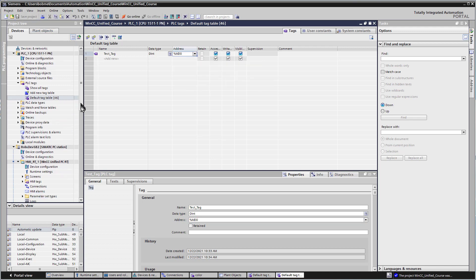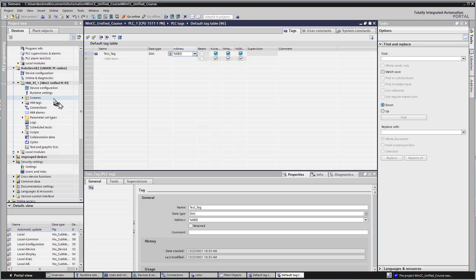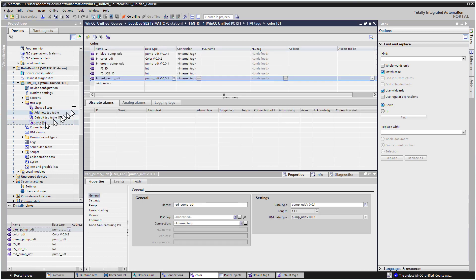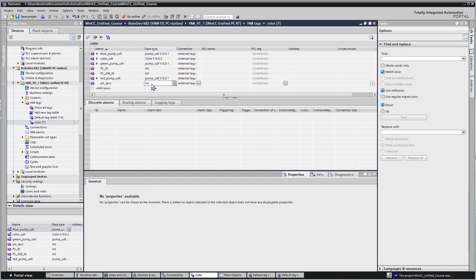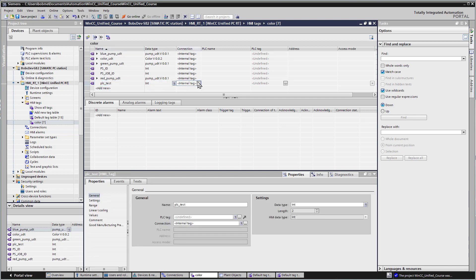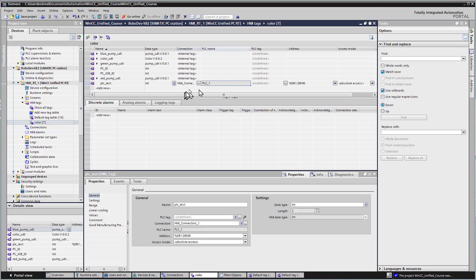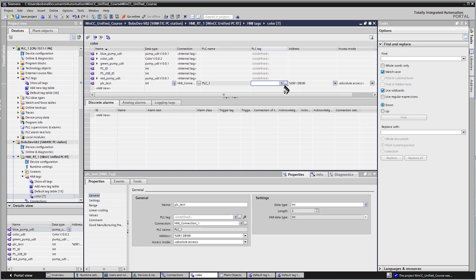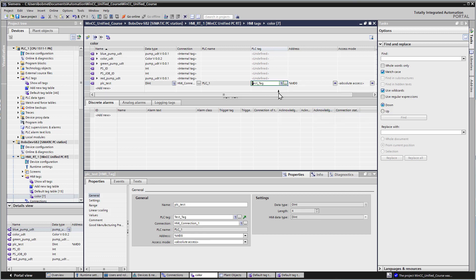I'll save that, and then we'll come down to the runtime, go into our HMI tags, and I'll use our color tag table and add new. I'll create a tag called PLC test. For our connection, it should find HMI connection 1. It knows that we're talking about PLC 1, which is our new controller that we just added. Under our PLC tag, I can add my test tag and save that.